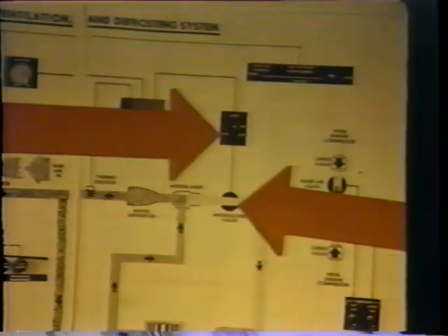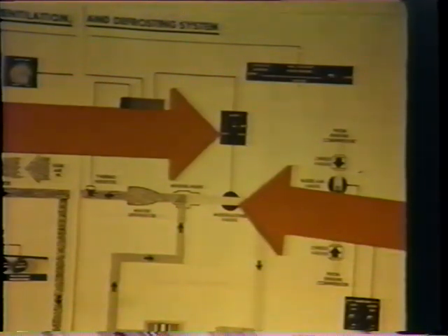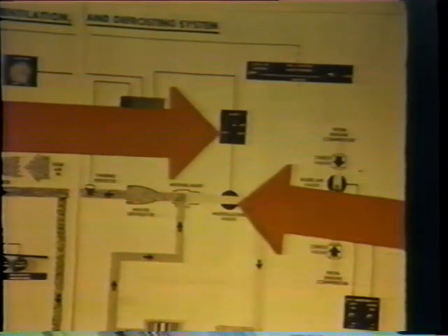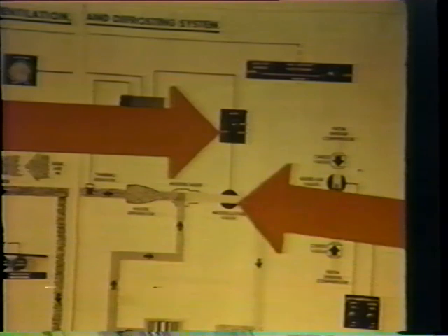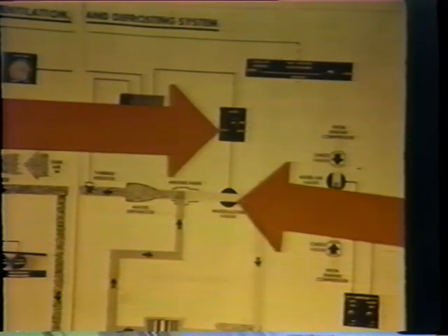Both hot and cold positions are spring-loaded to center and must be held to hot or cold until the modulating valve is in the desired position. The off position removes power to the valve, and it will remain in the last position selected.